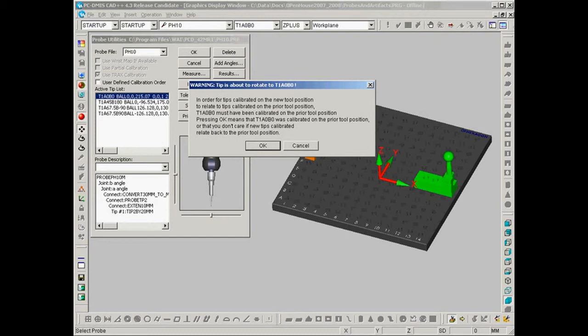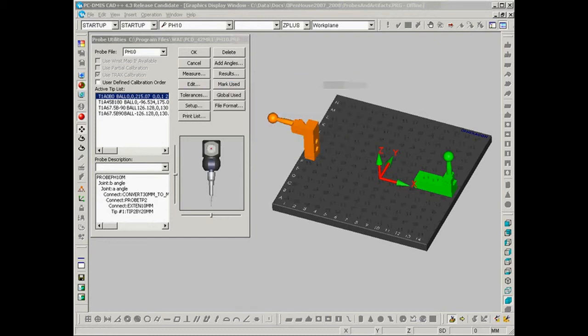So now PC-DMIS knows the location of my green calibration sphere. What we need to do now is locate the orange calibration sphere in relationship to the green calibration sphere. So we're going to go back and we're going to select measure.